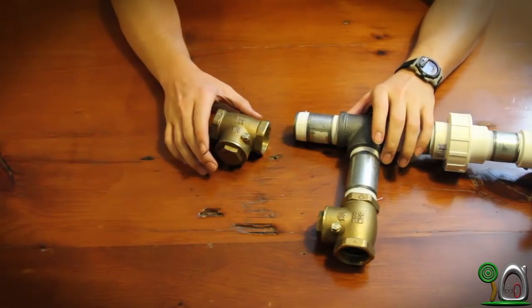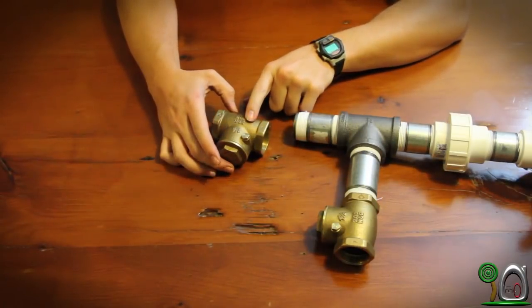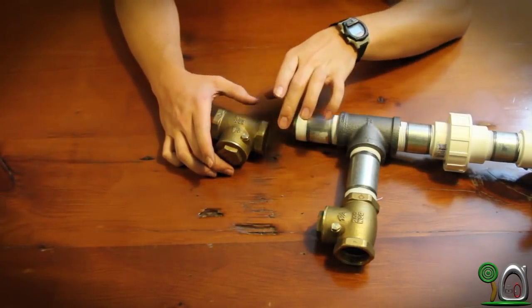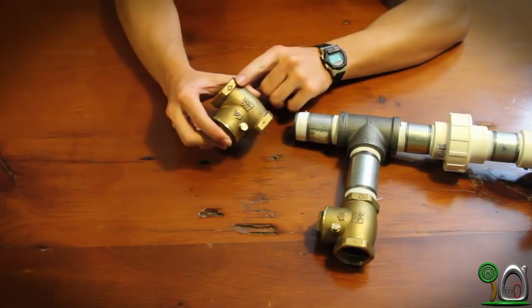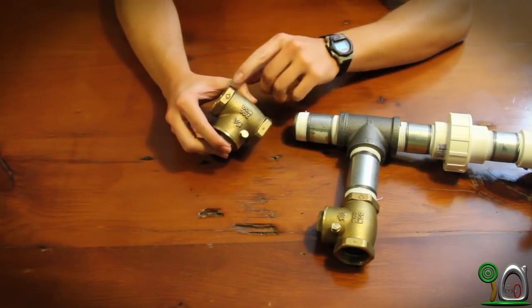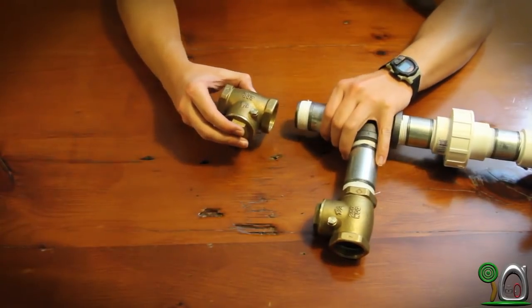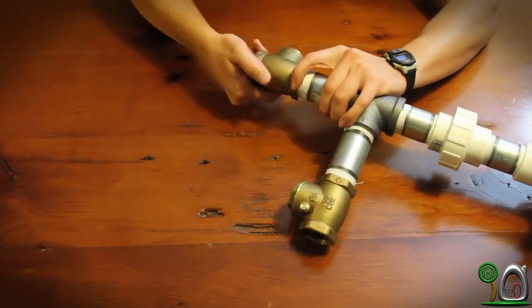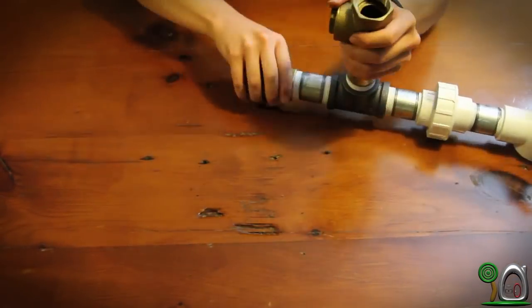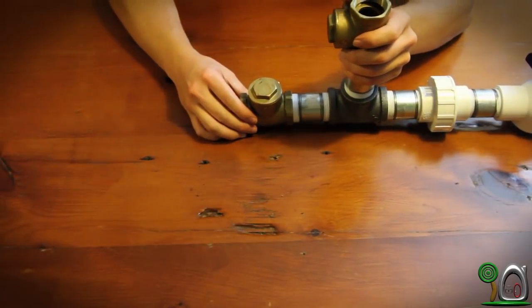Step 9. We're going to attach the other check valve or swing valve. This time, the arrow, or direction of flow, needs to be facing away from the rest of the system we've built so far.